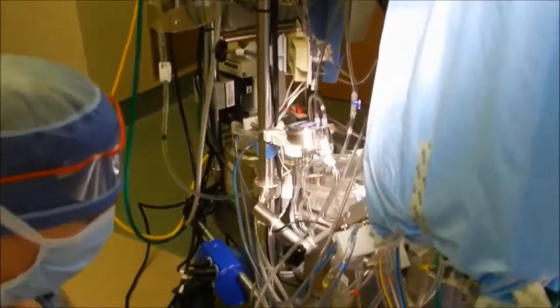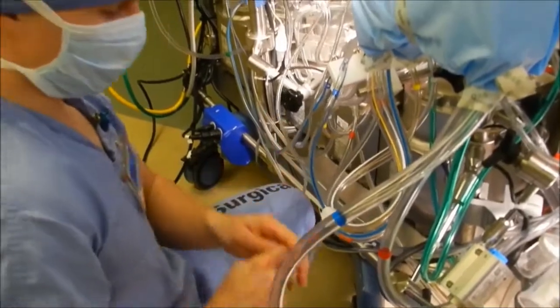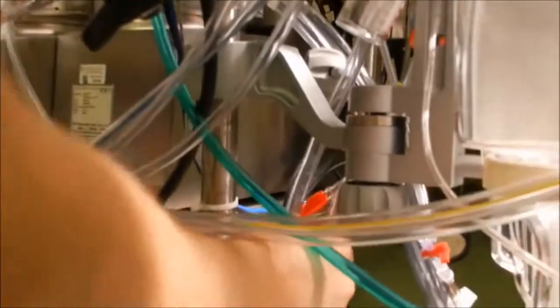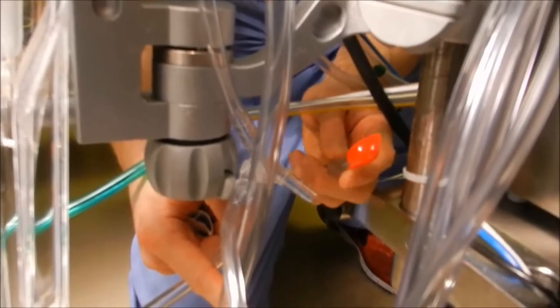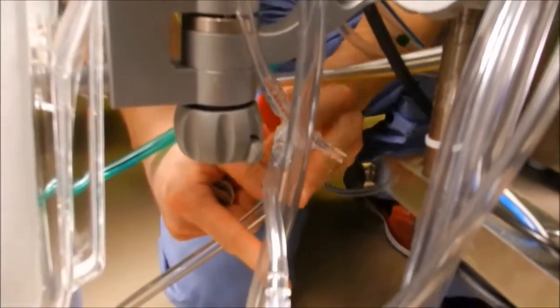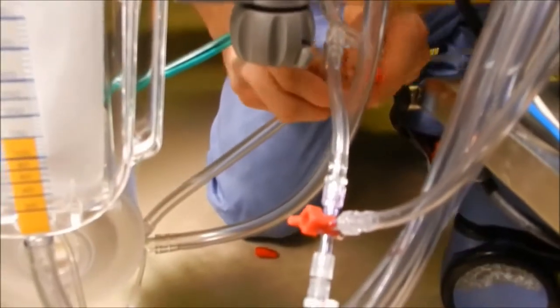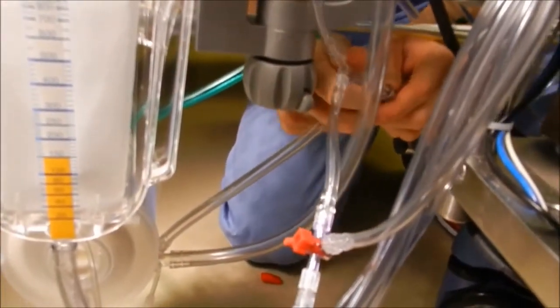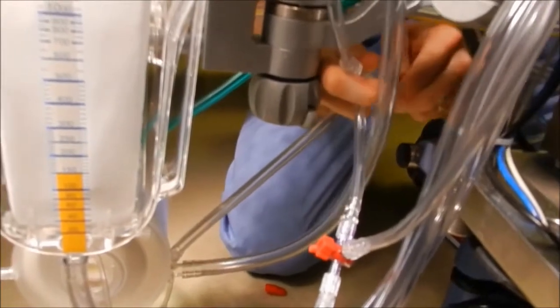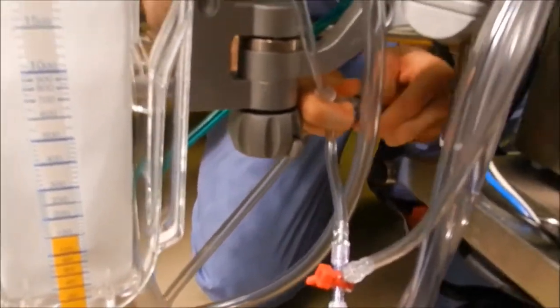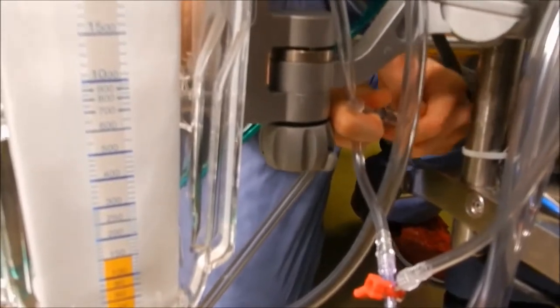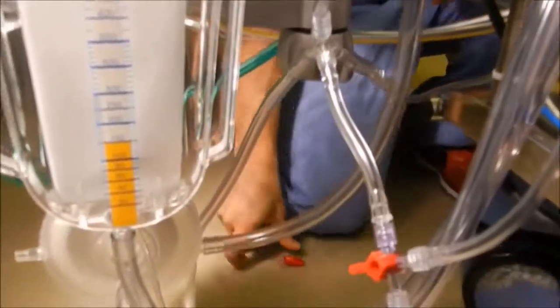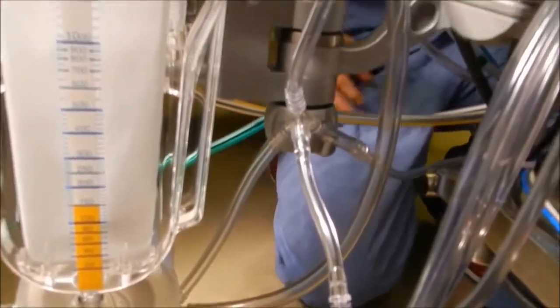As I walk around, we have our cardioplegia line, which will connect to our cardioplegia connector. It's a 1/4 inch stub that will connect to our Y off the cardioplegia outlet from our oxygenator. And we push that on there. Try to go for the 2 barbs. It's a tough connection to make.